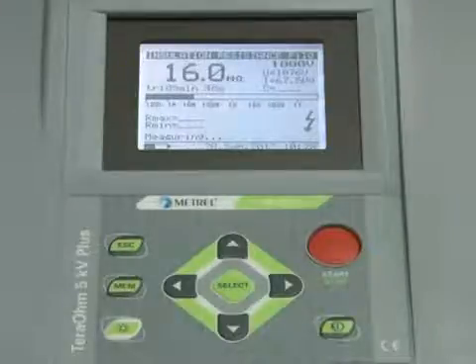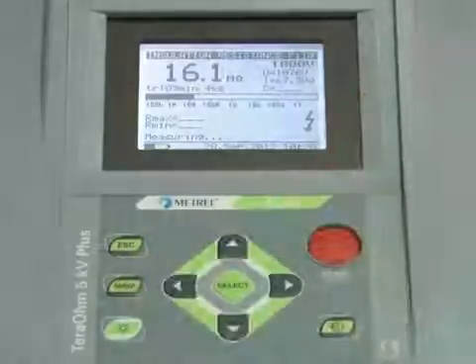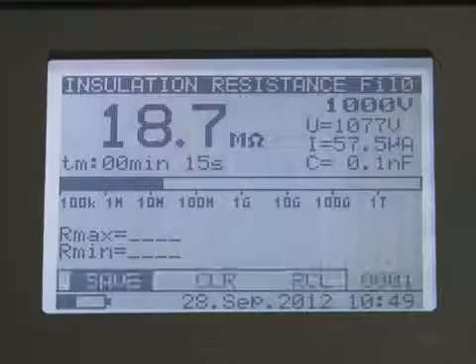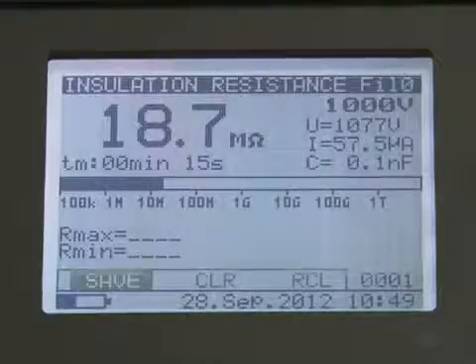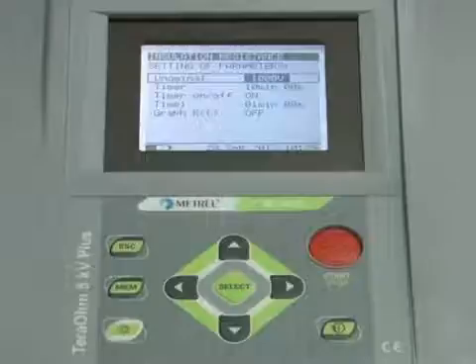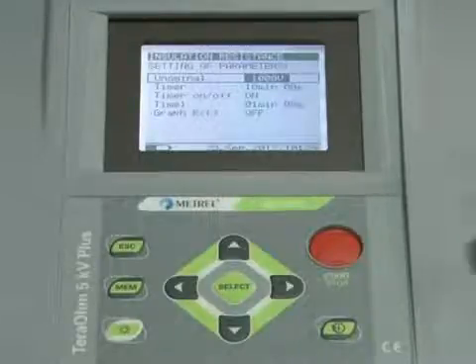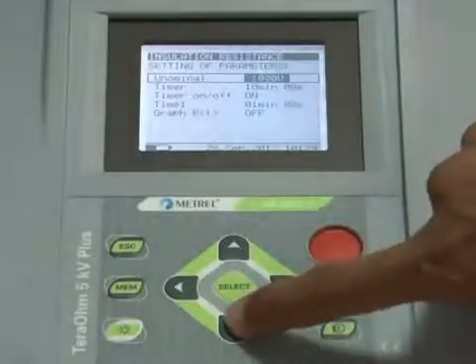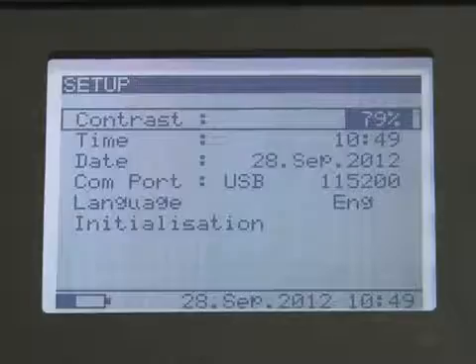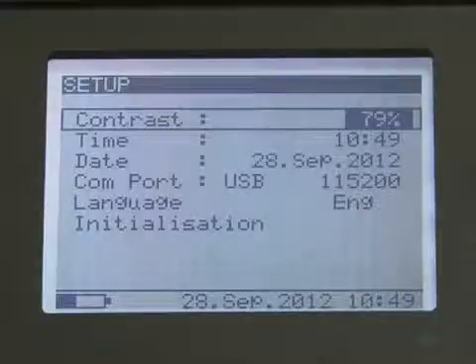Once the object is discharged, the user can save the result in memory by pressing the memory key twice. The user can view graphical and numerical data on the screen. In the settings, the user can configure the test voltage, duration of measurement, and the time period to accept and display the minimum and maximum values of resistance.